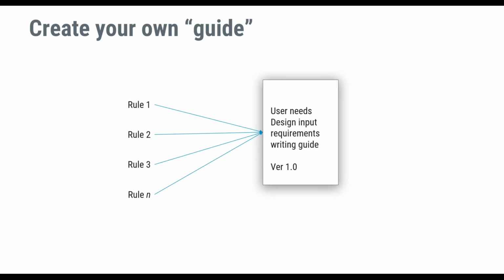So what do I think you should do about all these things? Well, I think you should create a requirements authoring guide, a document that says this is how we write user needs and design input requirements. Actually, I think it's worthwhile defining both those two, and they are quite different. And include maybe not all 36 or 41 rules at once, but if you include a number of them, you're going to get really far and see improvements in the quality of requirements.